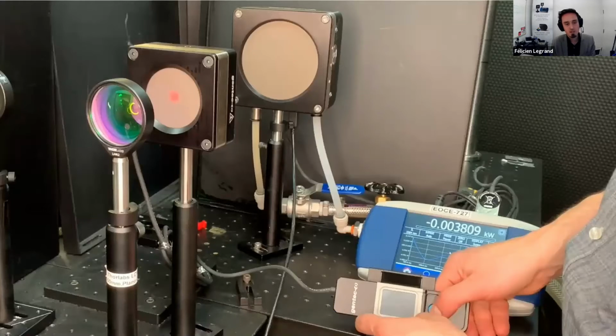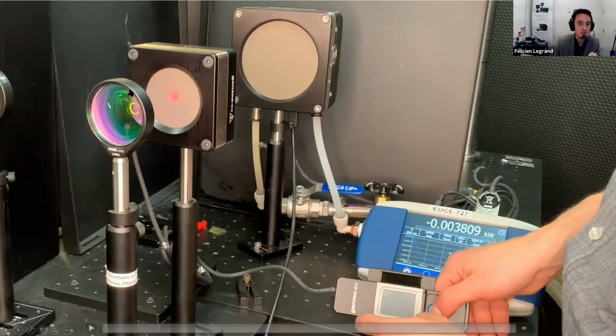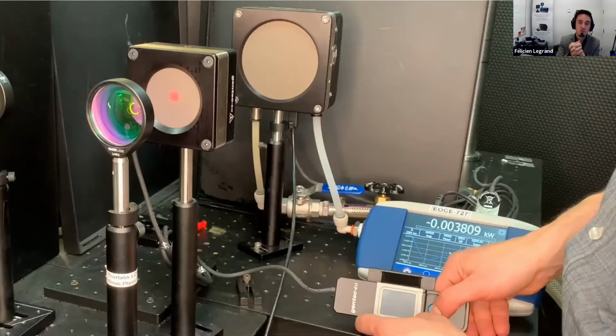Okay, so here I'm going to show you an example of measuring the power of a laser beam. This is a laser we're using in a calibration lab that goes up to 5 kilowatts. I'm going to show you a couple of tools here. First of all, we have a beam expander on the left hand side, which is used to simply enlarge the laser beam size to be sure we comply with the damage threshold and to be sure we have repeatable measurements using these absorbers.